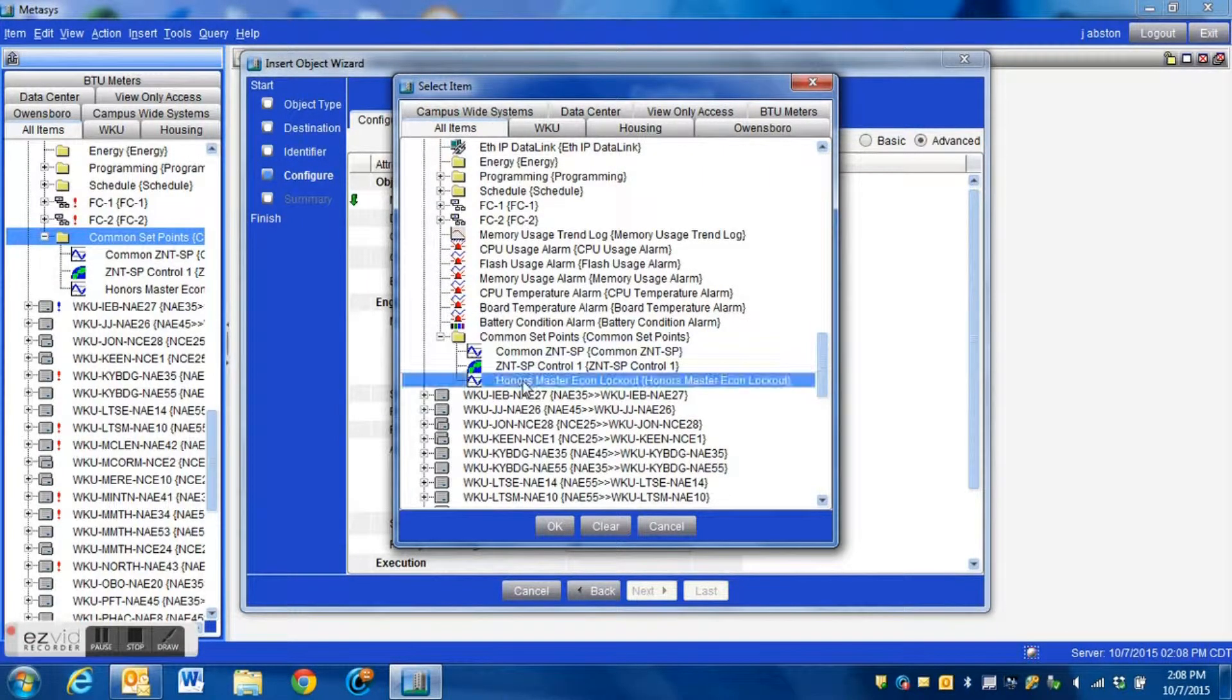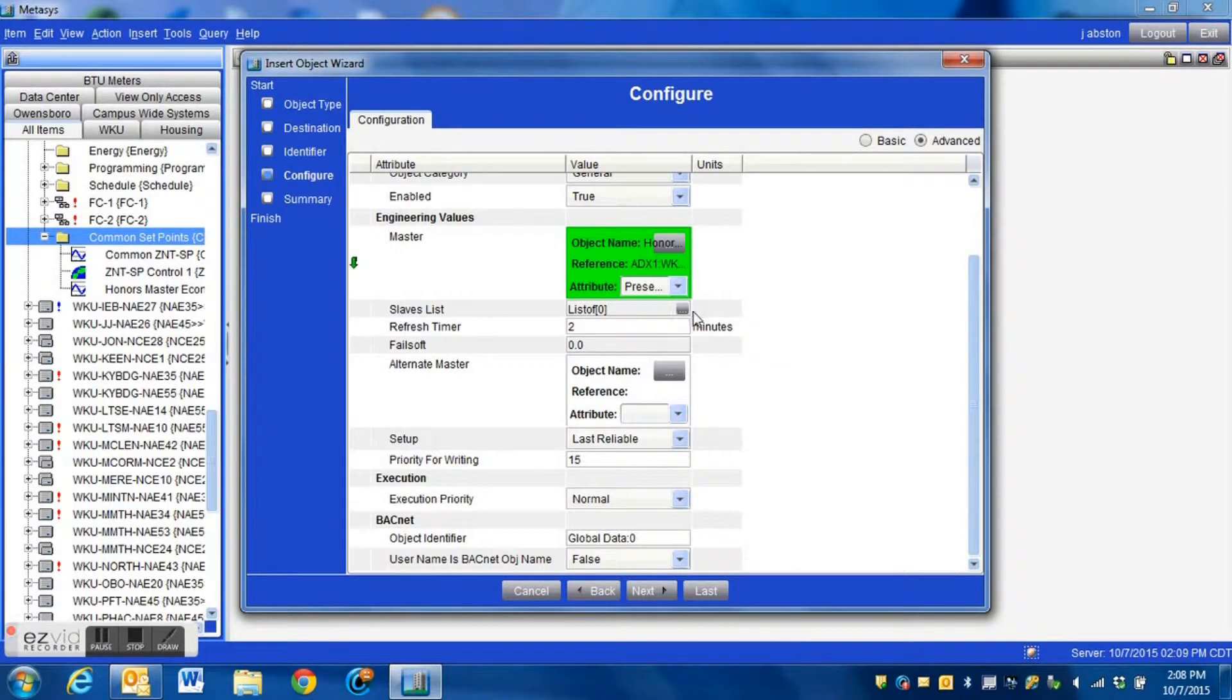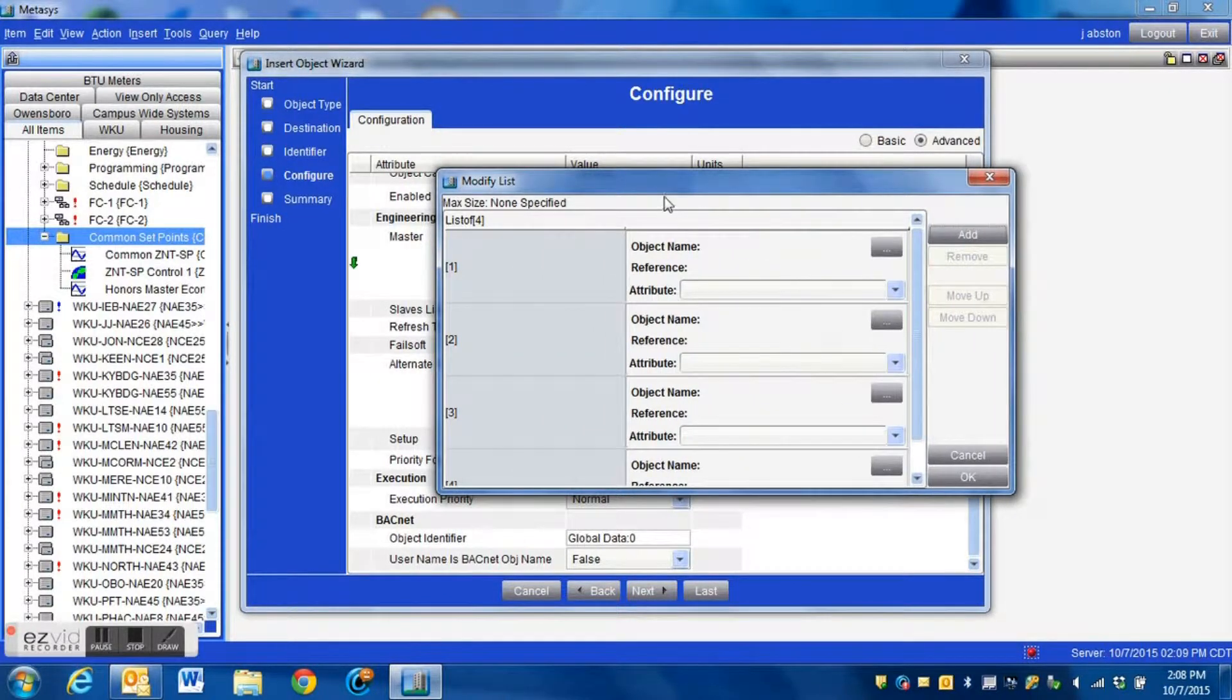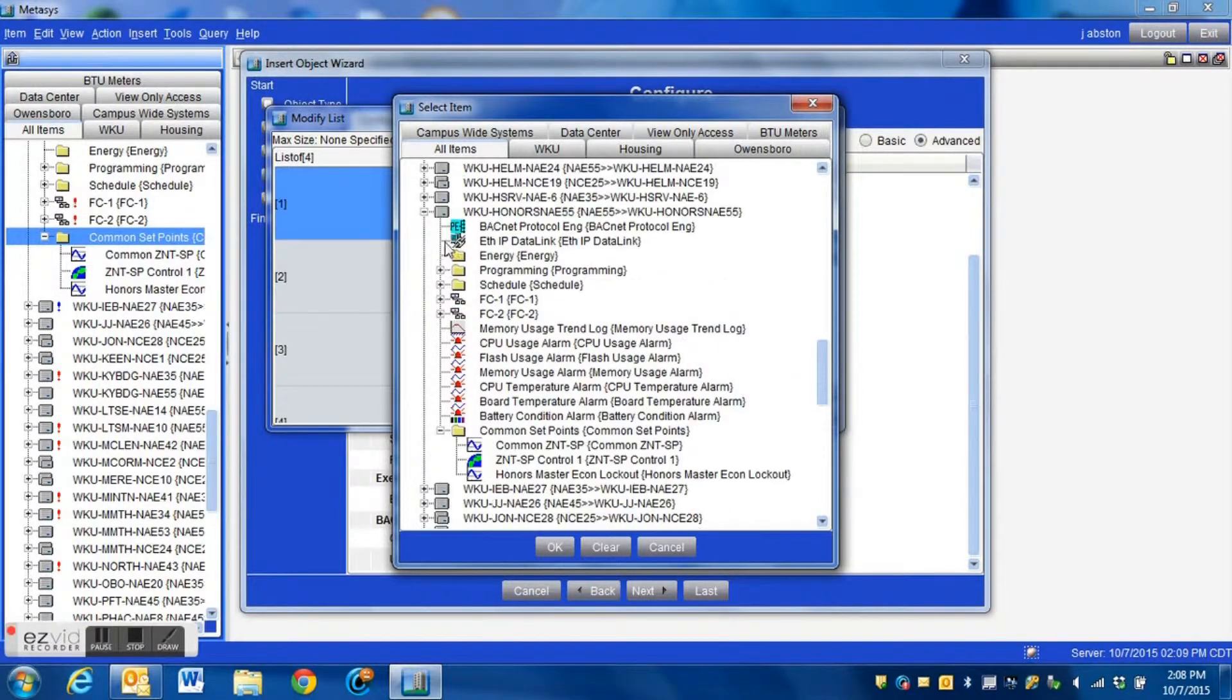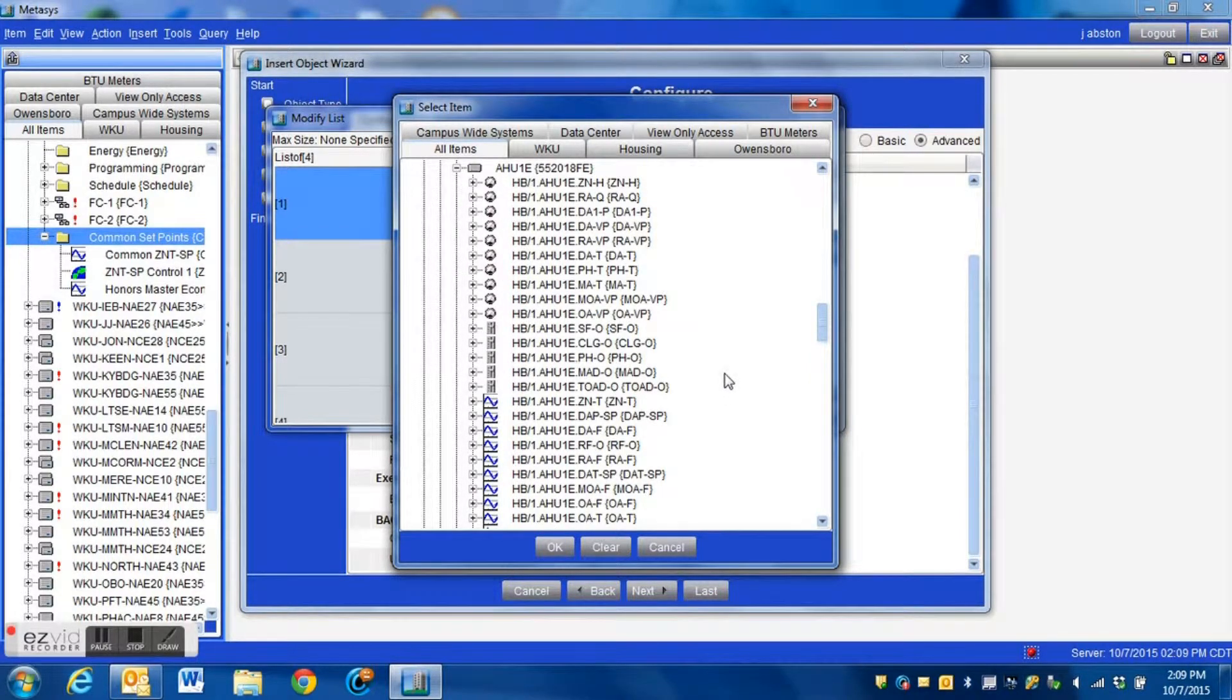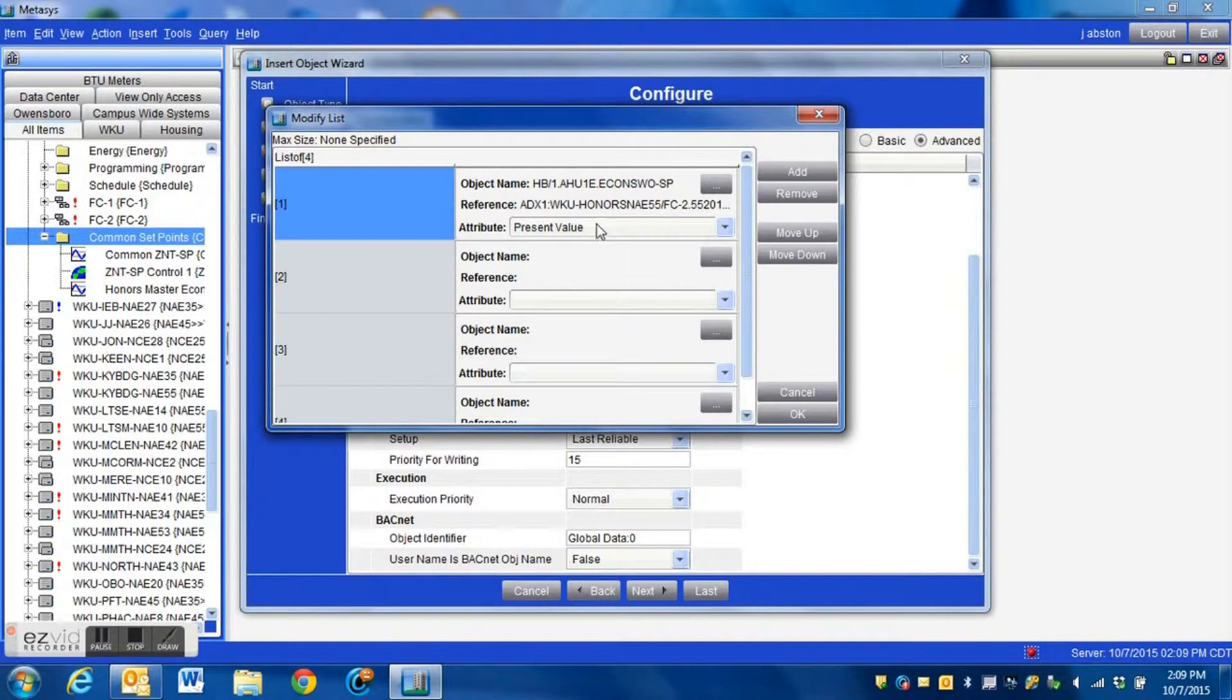Once we do that it will link the global data block to that point and now we have to create our slave list. This is a list of points which that value will be written into. We hit this and we're just going to create a few here. We're going to make our screen a little bigger to make it easier for us and each of these has the option of going in and selecting the various points. Now we're going to go down to our network and actually select the economizer switchover setpoint for each of our air handlers.